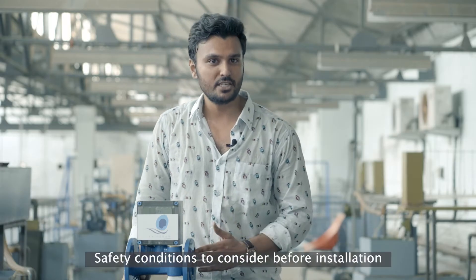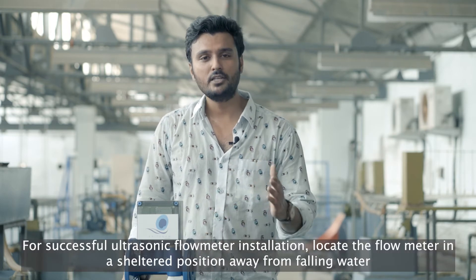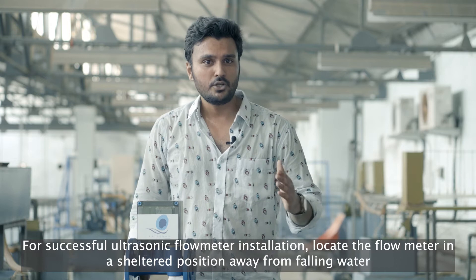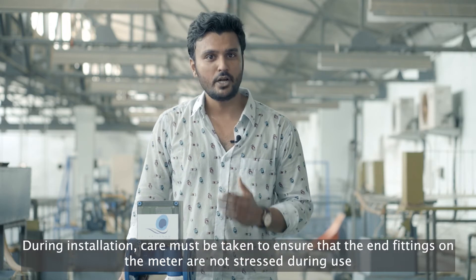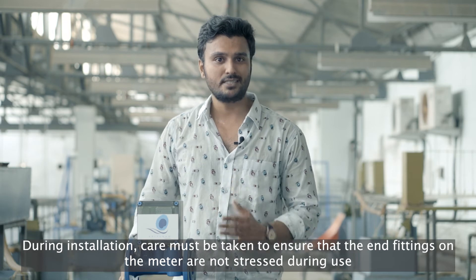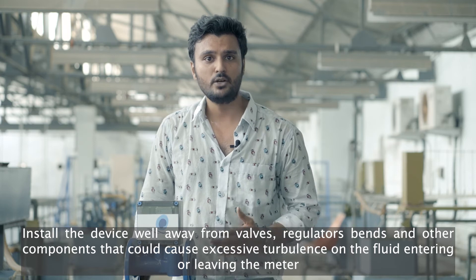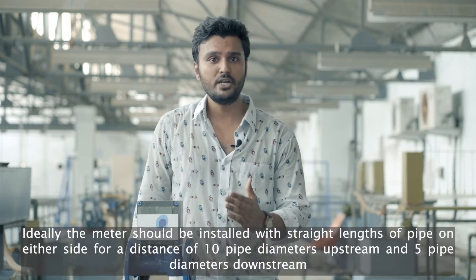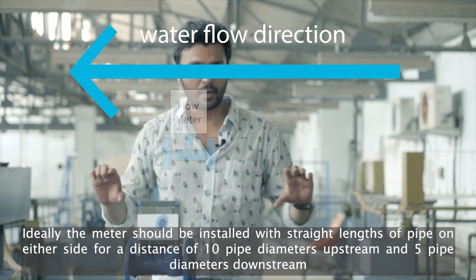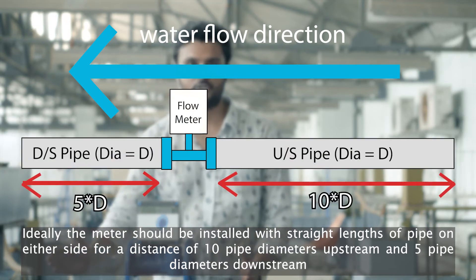There are some safety conditions to consider before installation. For successful ultrasonic flow meter installation, locate the flow meter in a sheltered position away from falling water. During installation, care must be taken to ensure that the end fittings on the meter are not stressed during use. Install the device away from valves, regulators, bends and other components that could cause excessive turbulence on the fluid entering or leaving the meter. Ideally, the meter should be installed with straight lengths of pipe on either side for a distance of 10 pipe diameters upstream and 5 pipe diameters downstream.